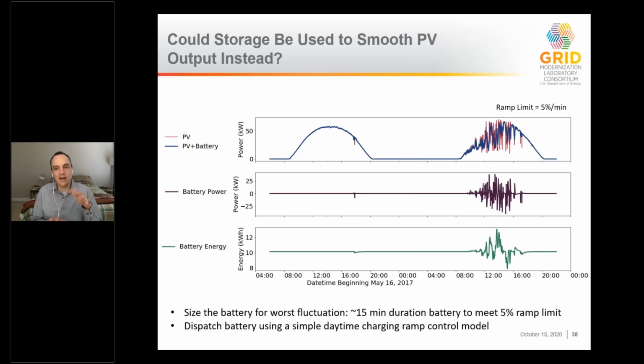And then the battery size itself, the capacity of the battery, was sized similar to the PV plant. So in this case, it was like a 75 kilowatt PV plant. And so we also had similarly like a 75 kilowatt battery. But the amount of energy that that battery needed to store was relatively small. So at full power, that battery would be completely discharged in 15 minutes. And that was sufficient to be able to cover all of these conditions, including this partly cloudy day where you saw a lot of rapid output changes from the passing clouds. Next slide, please.